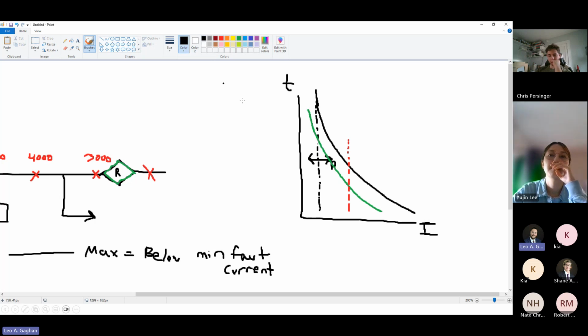So your other setting to make this happen is something called a time dial. Your time dial is going to move you up and down. So as you adjust your time dial, you're going to go up and down. Right, you've got to pick your pickup based on your sensitivity and your loading, and your time dial you really play with just to get that timing that you want.